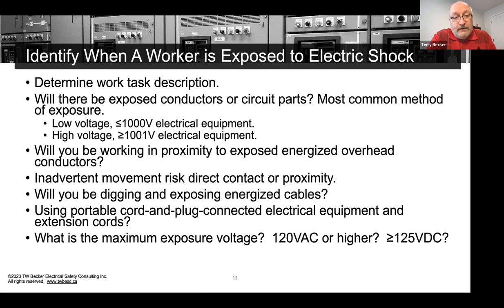The CE Code Part 1 in Canada, the 2021 edition, changed to these definitions of low and high voltage. So are we working in proximity to overhead conductors and circuit parts, you know, distribution lines, inside substations? Again, this is an all-worker topic for electric shock. Inadvertent movement risk or direct contact. And so for the low voltage, again, it's your hands going in with these test instruments, right, into those conductors with these probes. And that's been one of the problems: bare hands going in, inadvertent movement, momentary contact, momentary current flow into the body, pain, worker flinches out, and then they don't report that shock. That's sort of been the norm, all right?